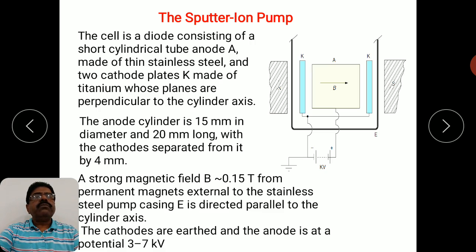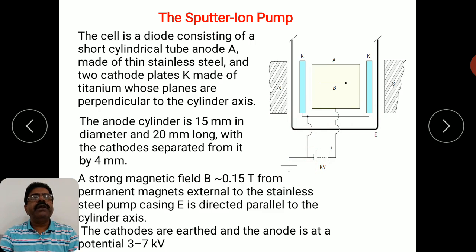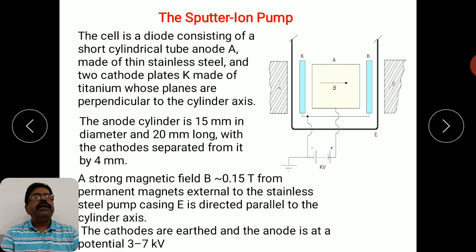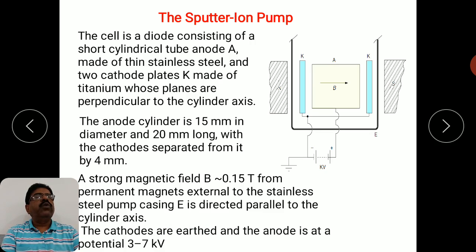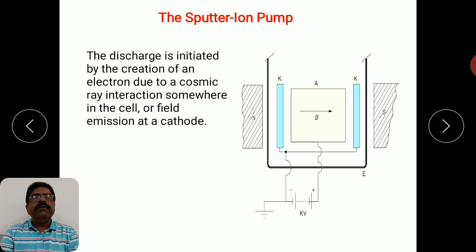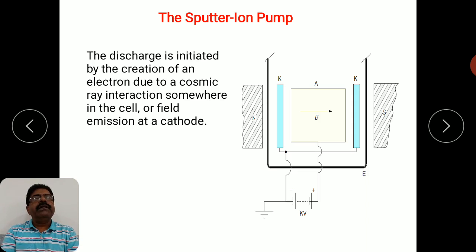The cathodes are kept at ground (earth) potential, while the anode is maintained at a high positive potential of the order of 3 to 7 kilovolts. We will now discuss the function of this Penning cell — how it acts as a pump and the meaning of the sputter ion pump.